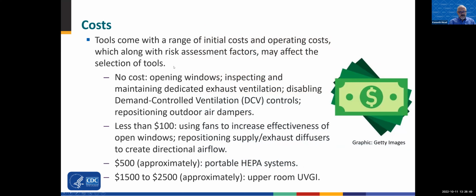We put some cost estimates down. These are first cost primarily, but it's important to consider that all interventions have both a first cost as well as an ongoing or operating cost. First cost for things like opening windows, doing your inspections, and disabling demand controlled ventilation through the flip of a switch: those are generally free interventions that you can invoke rather quickly and at minimal cost. Less than $100 for using fans to augment, opening windows, repositioning supply. Portable HEPA systems, approximately $500. The price of those has actually come down quite a bit as the pandemic has progressed. And then a UVGI system, a ballpark $1,500 to $2,500 per fixture.